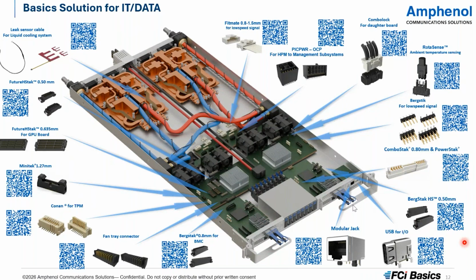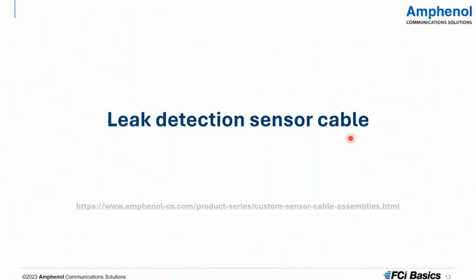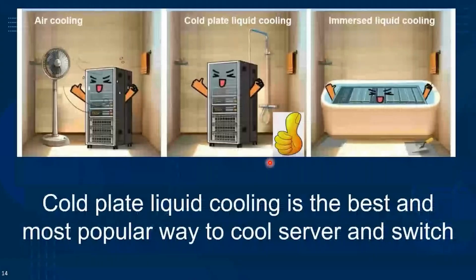Now I'll pick some products to go through in a little more detail. First of all, I'll present our leak detection sensor cable solutions. There are three types of cooling system for data center heat dissipation. The traditional way is using fans for air cooling. Immersion liquid cooling is an option, but it's too expensive and not easy to maintain. So currently, cold plate liquid cooling is the best and most popular way to cool AI servers and switches.